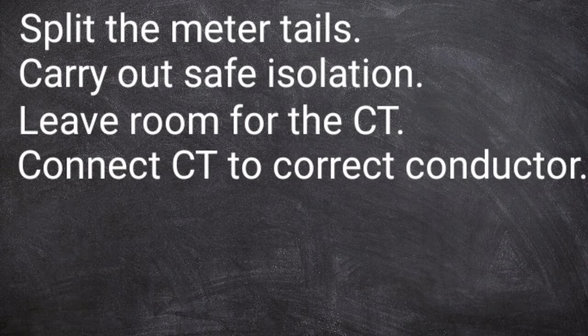And it's important that you select the outgoing line conductor from the kilowatt hour meter that feeds into the Henley blocks, but not individually to a separate consumer unit or a separate consumer you've installed for the EV charging point. And just further to that, it's really critical as well that we get the CT pointing in the right direction. So you look at the base of it, it's got an arrow on it, and that current should be pointing effectively into the installation away from the energy meter. So that's a critical point as well.